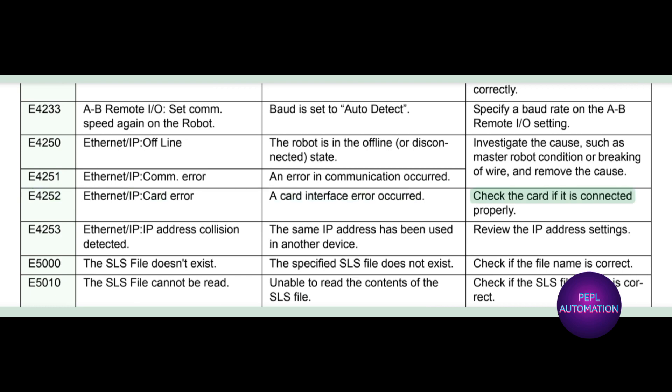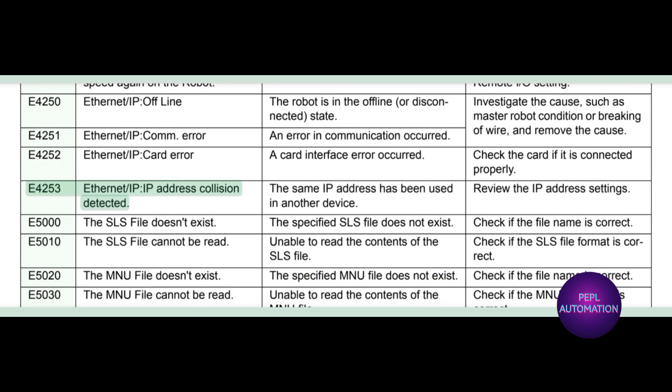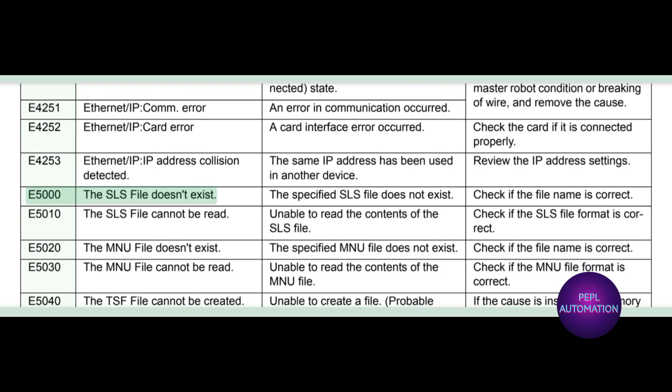E4251 Ethernet IP com error: an error in communication occurred. E4252 Ethernet IP card error: a card interface error occurred. Check the card if it is connected properly. E4253 Ethernet IP IP address collision detected: the same IP address has been used in another device. Review the IP address settings.